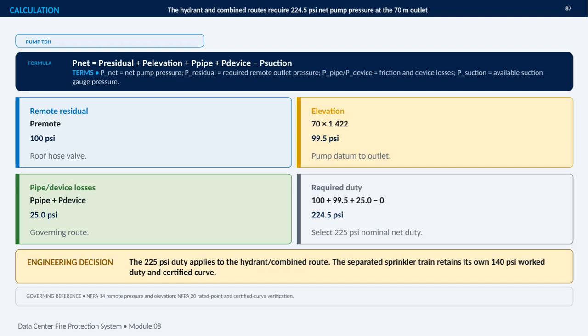This slide calculates the pump pressure required for the hydrant and combined routes, using the remote roof hose valve as the governing outlet. The calculation starts with the required residual pressure at that outlet, which is 100 psi. We then add the elevation pressure from the pump datum to the 70-meter outlet, 70 multiplied by 1.422, or 99.5 psi. Finally, we include 25 psi for pipe and device losses along the governing route and subtract available suction pressure.